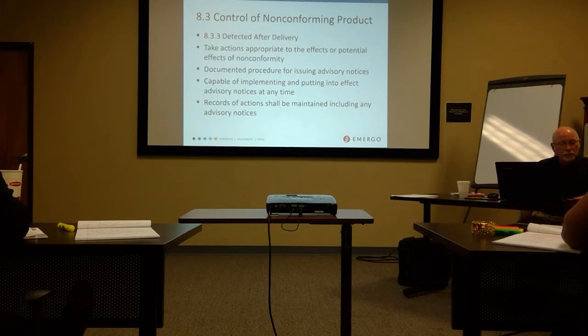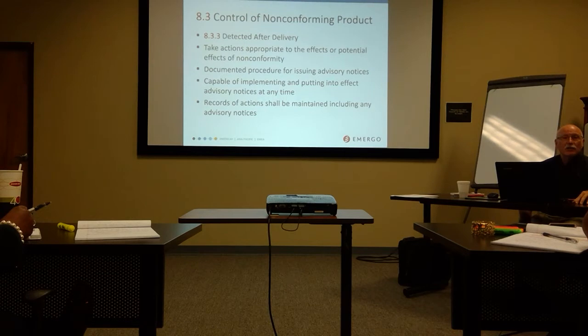There's one situation that I can envision where you detect a non-conformance after delivery, but before it generates a complaint. In that situation, I think I would just use my complaint process and make sure I advise the user, hey, we found this issue, be advised, service notice or whatever, and take whatever action might be appropriate. This is a new addition where they actually made this distinction between these two, and they probably need to embellish this a bit and really draw the distinction between the complaint process after delivery and found by the customer, and after delivery but not found by the customer. Now what do I do? I'm not aware of any specific requirements around that yet. It's probably something to see evolve over time.